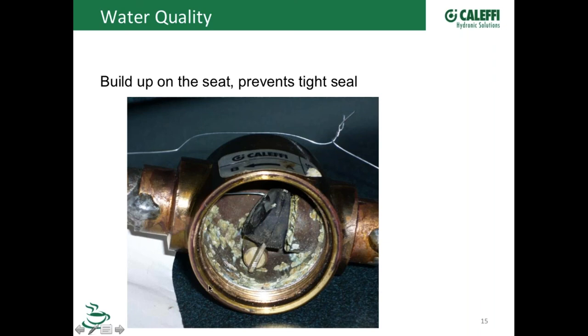And another great thing to mention on this slide too is, for open systems, we do actually manufacture a handful of lead-free or low-lead zone valve bodies that will meet the low-lead requirements for domestic hot water applications. Now, they're typically not used for a shutoff type valve. We talked about the maximum differential pressures before, but if you're using domestic hot water to flow through fan coils, or whatever the case may be, or through baseboard, you can use some of our zone valves for it as well, but just make sure that they are the lead-free models.